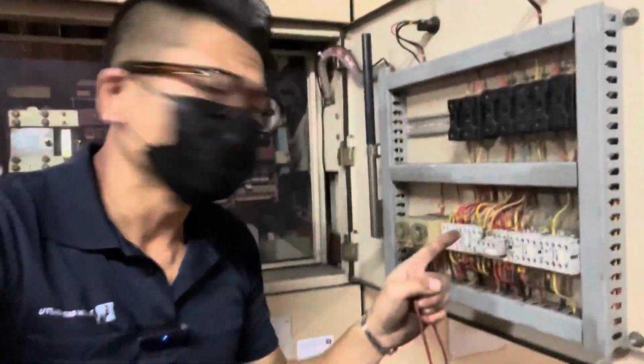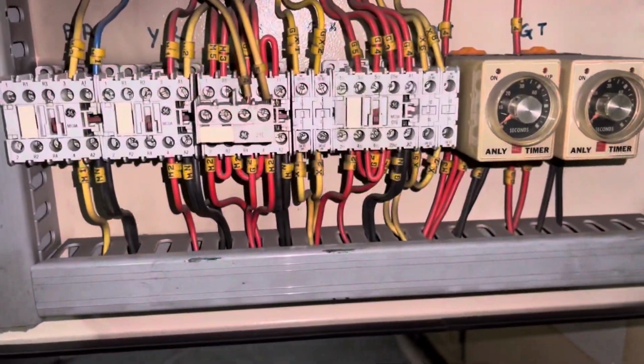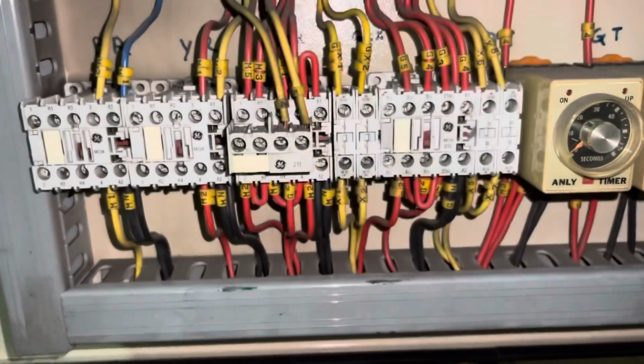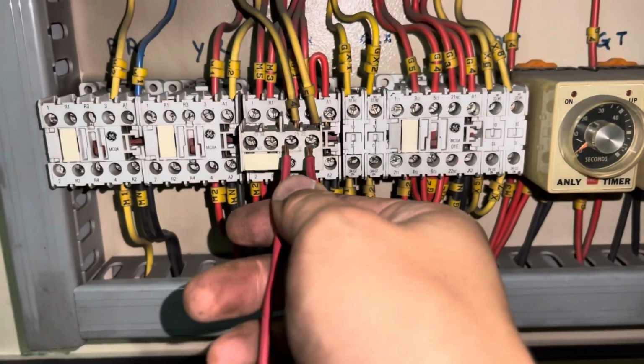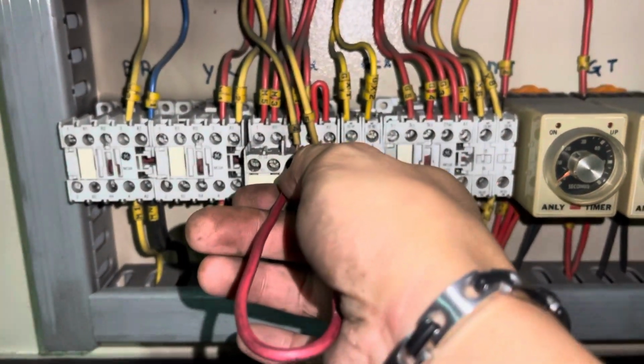Okay, to test the genset remotely from the ATS panel, I'm going to use this jump wire. Okay. This is the ATS panel. I'm going to jump between those two terminals. Alright. Terminal number 4 and 5. Okay, let's jump in.